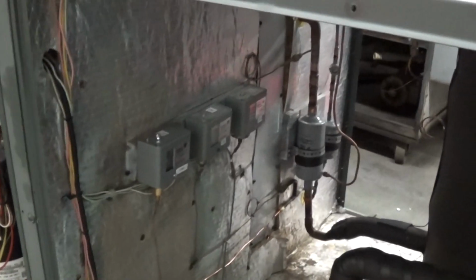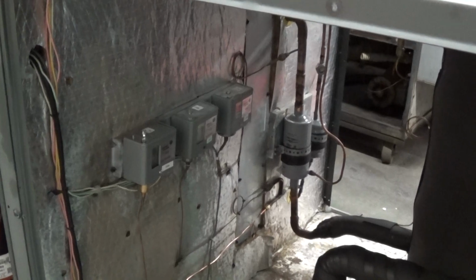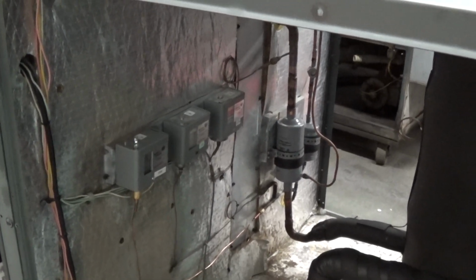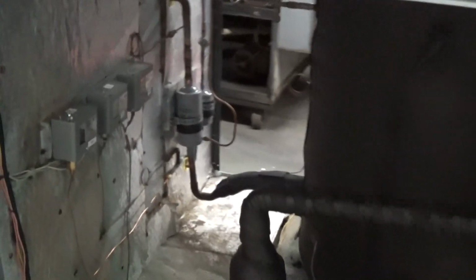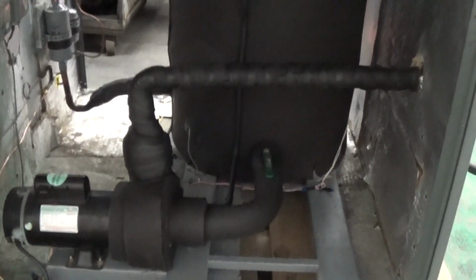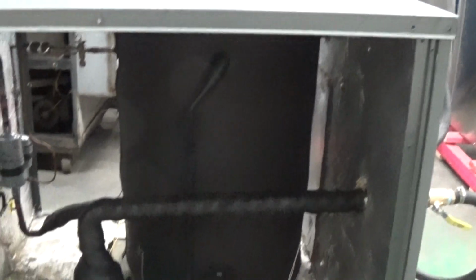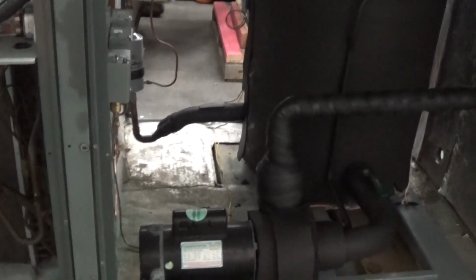Here we have the high-low pressure switches and the switch for low ambient, the fan switching. This unit here, we also put in a fresh charge of our 410A refrigerant because when we did take the whole tank out, we had to cut some of the lines. Not a big deal, but just kind of the right thing to do.